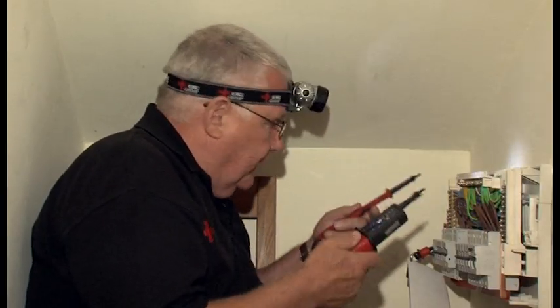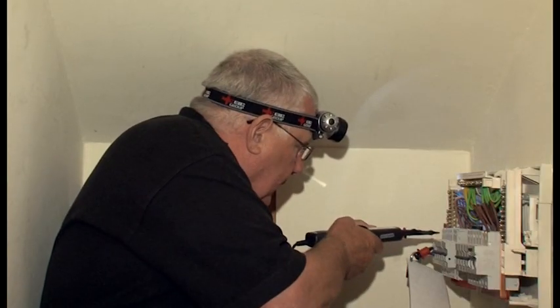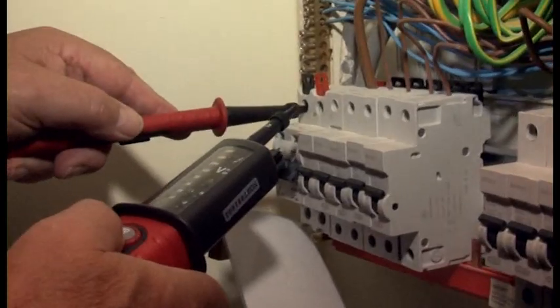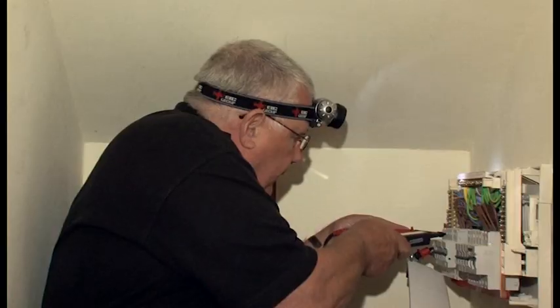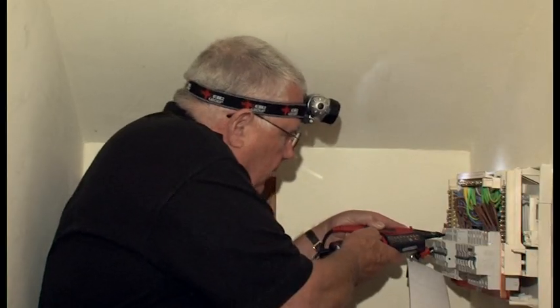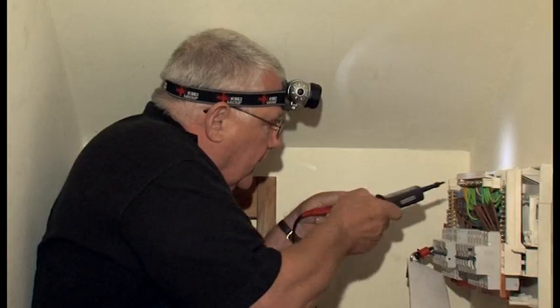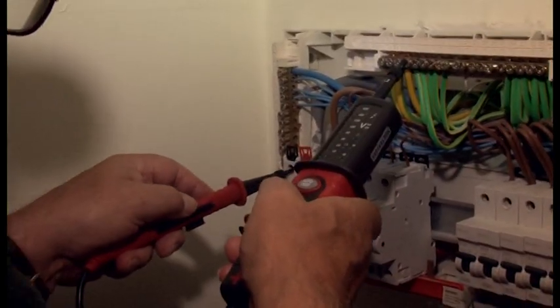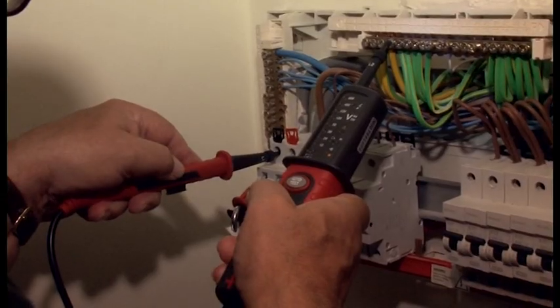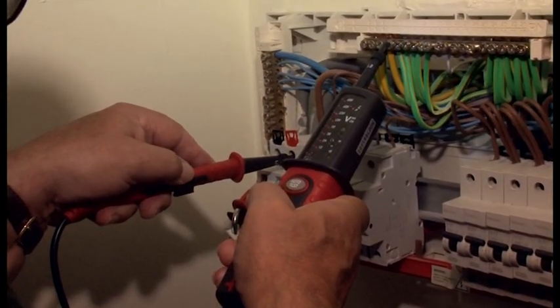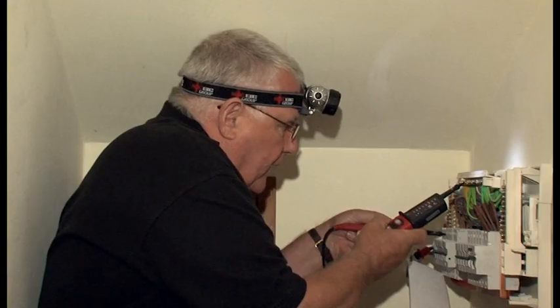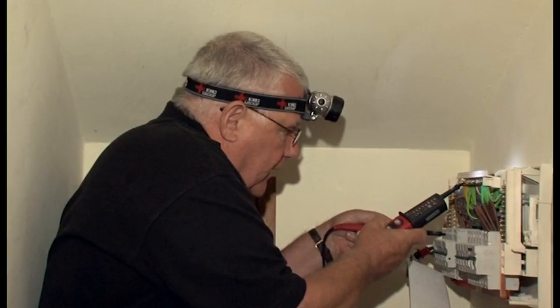What I'm going to do here, I've got my voltage checker. I'm going to actually check the incoming supply first. Remember, always go on the neutral first. And you see there, we've actually got a live. Now what I'm going to do is check polarity. So I'll actually go onto the earth. I'll go onto the neutral. As you can see, we've got nothing there. So if I go onto the line, there we can see that we actually got correct polarity for this installation. So the polarity test is correct. So let's now move on to our test which will verify ZE, the impedance of earth external to the installation.